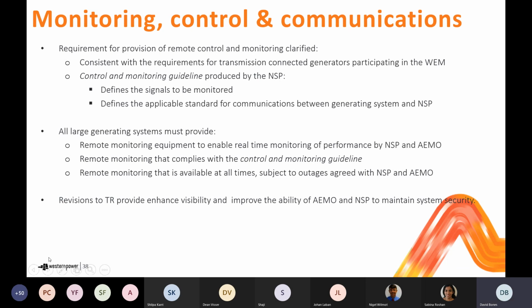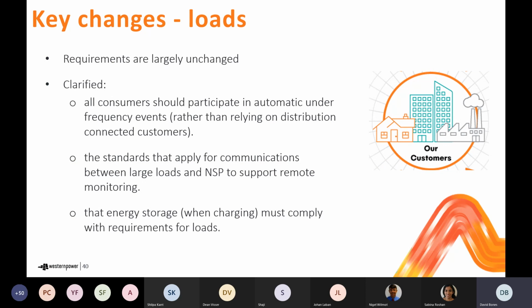I'd now just like to step through the requirements that apply to loads. In general, there's been very few changes to the user requirements for loads. A couple of the key changes are highlighted on this slide. So we've adjusted the drafting to make it clearer that there's an expectation that all loads should participate in helping to address under frequency events. So these are large under frequency events where you need automatic under frequency load shedding to help secure the power system and stop the collapse of frequency.